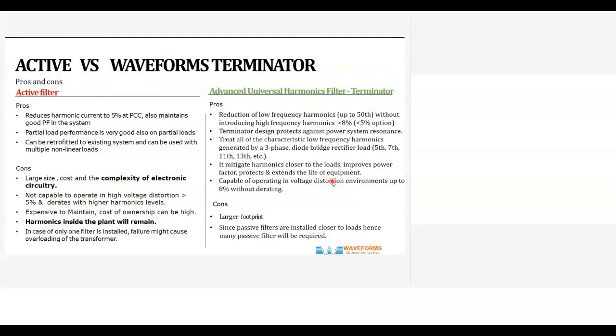But what happens is, you are sick, you're not taking the medicine, you are giving it to somebody else. So you don't clean up the harmonics inside your plant, and you are paying so much to reduce harmonics at the PCC. The harmonics inside the plant will still be circulating in other nodes and causing all these problems. So this is really not a good technique or good electrical practice. So that's an important point about this active filter. There are two points. One, it is very expensive, difficult to maintain, and the cost of ownership is high. Two, the harmonics inside the plant will remain. This is a key issue.